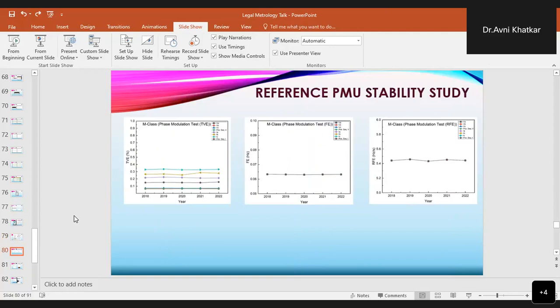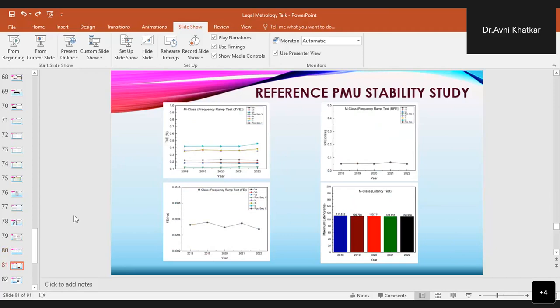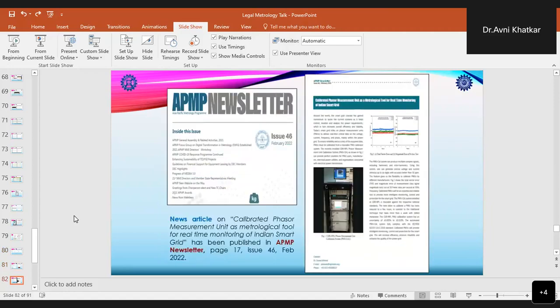Also, we have carried out the reference PMU stability study for a period of 5 years in order to see its stability, and the results show that the standard is very stable and no drift is seen over the period of 5 years. From the time it was installed till now, it is very stable. The results of this were also published in the APMP newsletter, and a news article was published on the calibrated phasor measurement units as a metrological tool for real-time monitoring of the Indian smart grid.